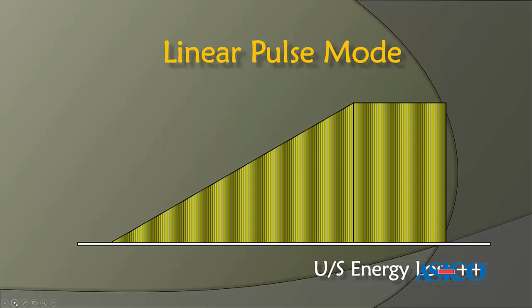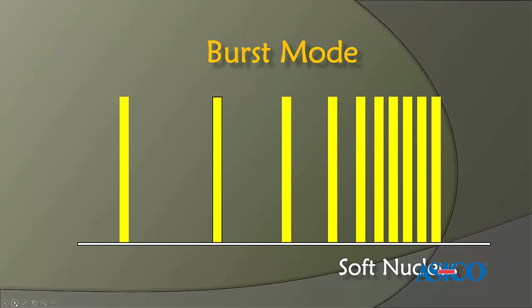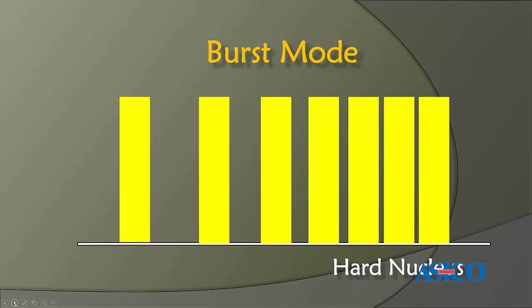If you use a pulse mode, there are so much loss of the ultrasound. In the pulse mode, the power is controlled by the foot pedal. On the contrary, in the burst mode, by the foot pedal, interval of the phaco emission is controlled. The interval is controlled by the foot pedal. For the soft cataract, I'll use a short burst, but for the denser cataract, I'll use a longer burst on time. I'll always combine both longitudinal and torsional.